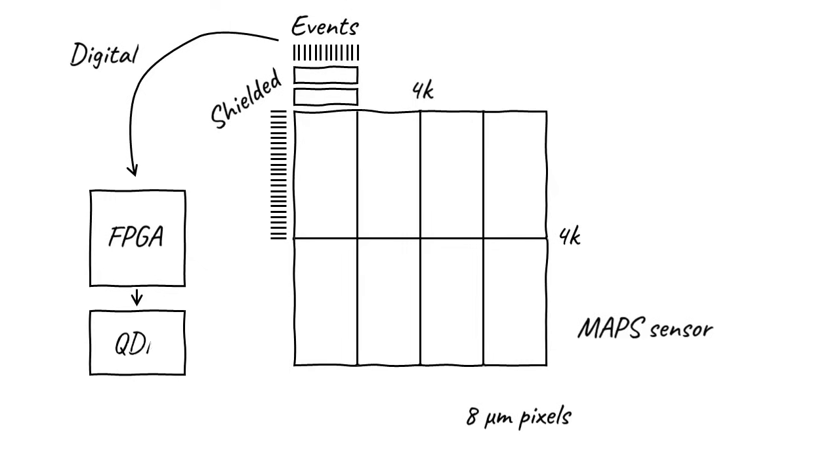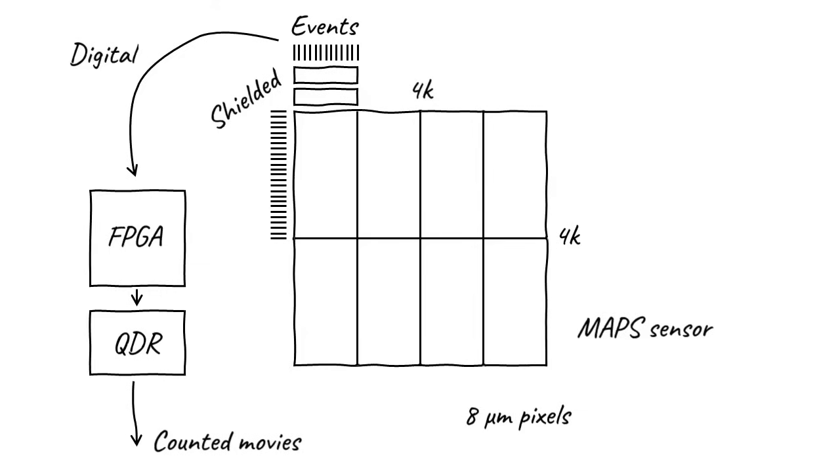This output is fed into an FPGA, or Field Programmable Gate Array, which is a powerful integrated circuit designed for real-time processing. The FPGA performs centroiding on each detected event, generating super-resolution, dose-fractionated movie frames in onboard memory. You may have heard of DDR memory, which stands for double data rate memory. Because of the extraordinary data rate in Apollo, it uses quadruple data rate, or QDR memory. Finally, these movie frames are output to the computer to be saved and used for image processing and reconstruction.